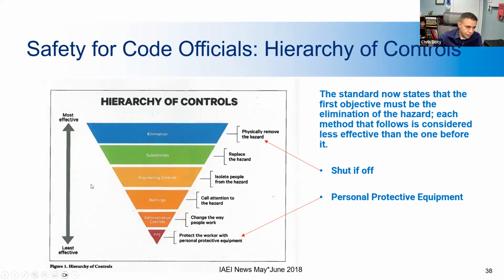So this is the hierarchy of controls from that standard. It's basically a method of evaluating and selecting the most appropriate method of protection for personnel. The best control is elimination of the hazard, which obviously makes sense. For electrical exposure, the best way is to shut off the power, then establish proper lockout tagout and verify that the power's off. That makes it so there's less human error involved, which is obviously better. Then the next thing down would be to replace the hazard. Then the next thing down is engineering controls, which is isolating people from the hazard. Then warnings, administrative controls, and then PPE. PPE is basically just living with the risk, and putting something on so that it will not be as bad. So that's obviously the worst one.